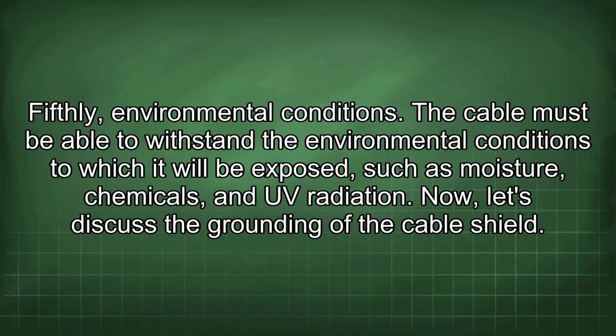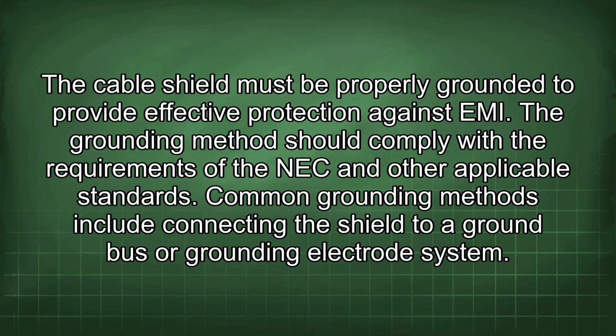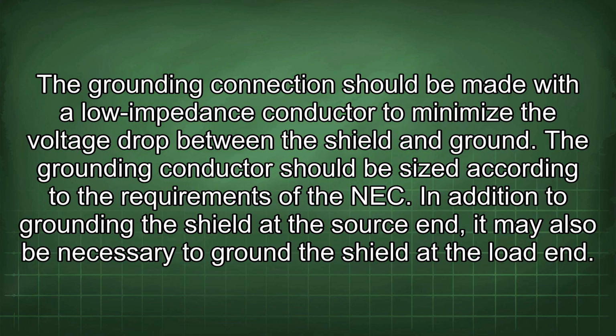Now, let's discuss the grounding of the cable shield. The cable shield must be properly grounded to provide effective protection against EMI. The grounding method should comply with the requirements of the NEC and other applicable standards. Common grounding methods include connecting the shield to a ground bus or grounding electrode system. The grounding connection should be made with a low impedance conductor to minimize the voltage drop between the shield and ground. The grounding conductor should be sized according to the requirements of the NEC.